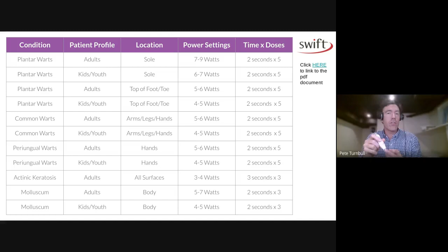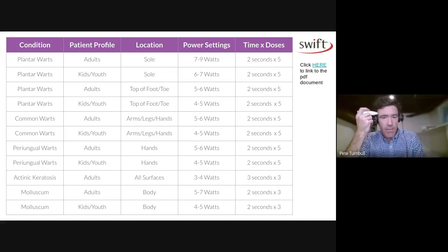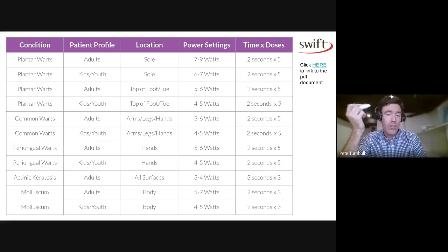As long as the probe is 7 millimeters, as long as the probe covers the full area, then you deliver 3 to 4 watts, so start at 4 if you can. If they find it too sensitive with 3 seconds, then you can take it back. I've been treating sebaceous hyperplasia on my forehead just as a test, doing 4 watts, 3 seconds. Actually, no, I've been going 5 watts, 3 seconds on my forehead, very thin skin, and I've found it quite manageable. So 3 to 4 watts on the leg should be pretty manageable from a pain perspective.